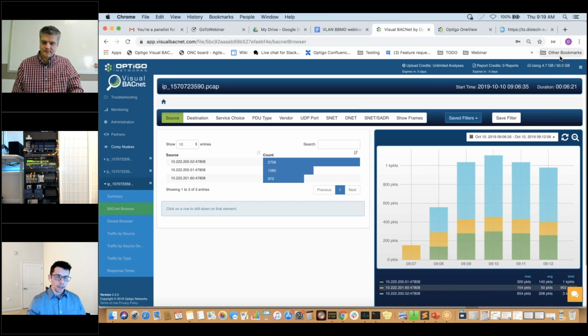But that's the idea. On a really large site, you've designed it in such a way that you only need, say, maybe a BBMD at the plant controller, and maybe you need some foreign devices up on the roofs with some air handlers and things like that. So BBMDs aren't bad. They're just bad when they're used across a site quite a bit. And if you have a large site and you're starting to get a lot of BBMDs, like 10 or 20 or 30, you really got to rethink that, because you're going to have a hard time troubleshooting issues.